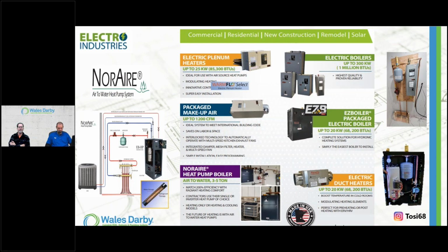Electric around here is expensive, so I was dragging my feet, thinking, why would we ever do this? And then application after application and learning, wow, there's some cool things about electric boilers. One, they get small. They get to loads that make sense. Sometimes even a turn down on a boiler, right? Again, I talked about this thing that hangs on the wall, and we think it's 96% because the tag says so, but you don't hook up an outdoor sensor, or do the combustion analyzer, or set up the parameters of lowering water temperature, achieving high efficiencies, right? So at best, maybe you're doing 82.